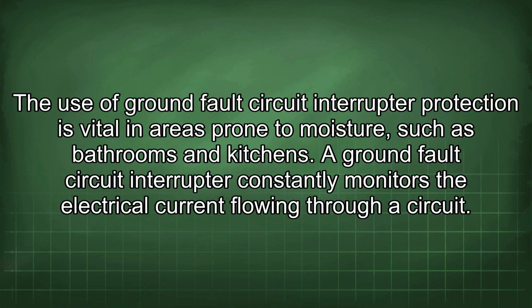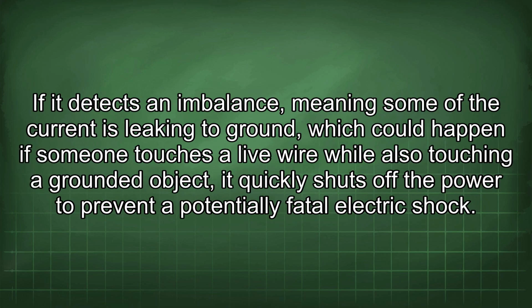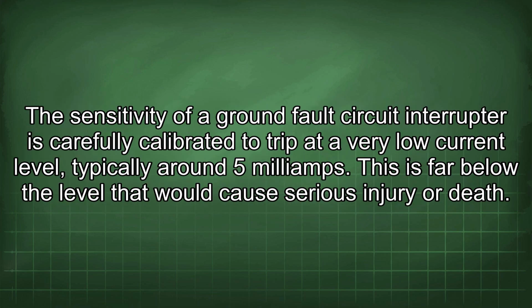The use of ground fault circuit interrupter protection is vital in areas prone to moisture, such as bathrooms and kitchens. A ground fault circuit interrupter constantly monitors the electrical current flowing through circuits. If it detects an imbalance, meaning some of the current is leaking to ground, which could happen if someone touches a live wire while also touching a grounded object, it quickly shuts off the power to prevent a potentially fatal electric shock. The sensitivity of a ground fault circuit interrupter is carefully calibrated to trip at a very low current level, typically around 5 milliamps. This is far below the level that would cause serious injury or death.